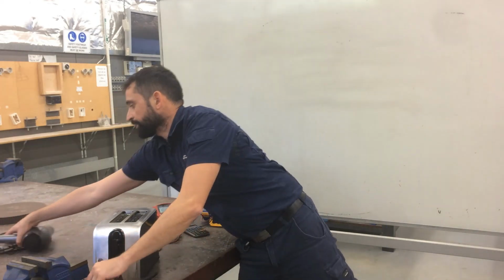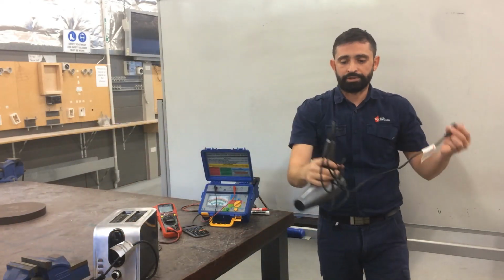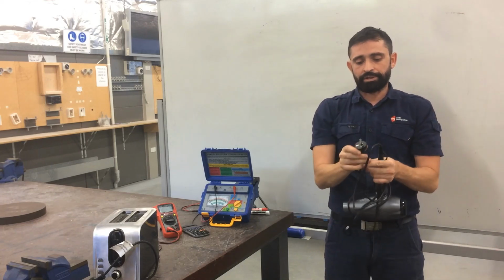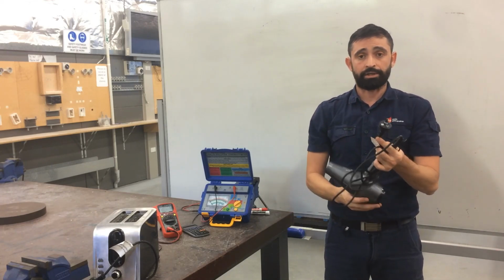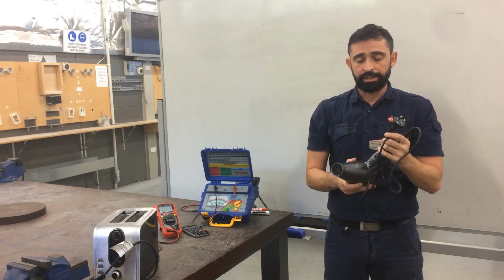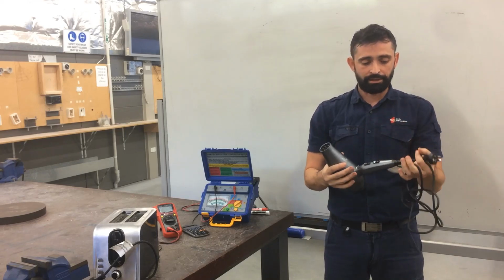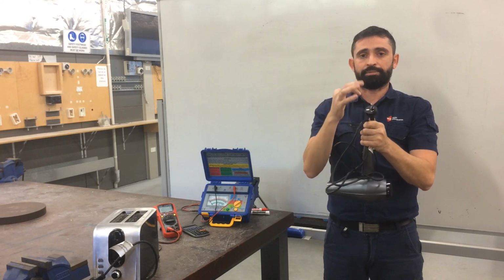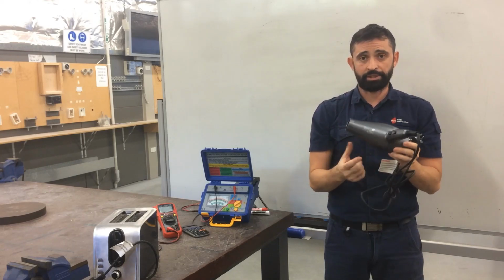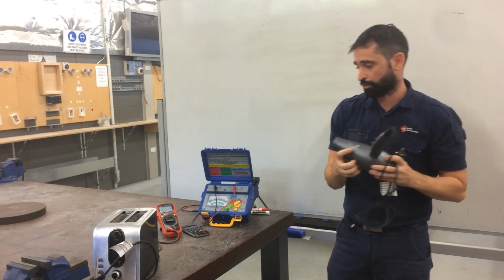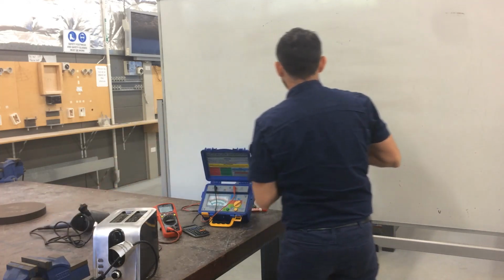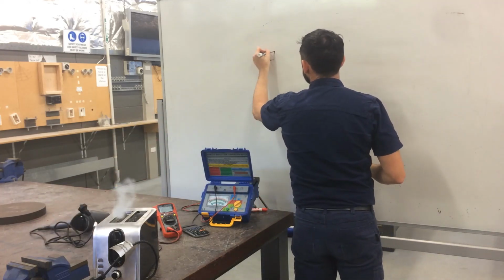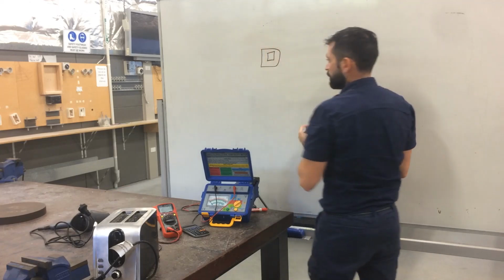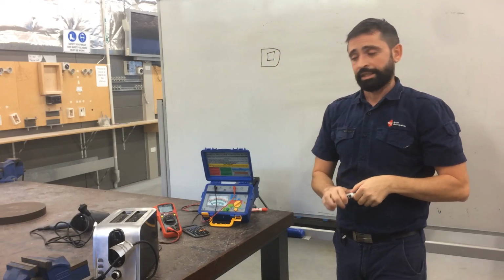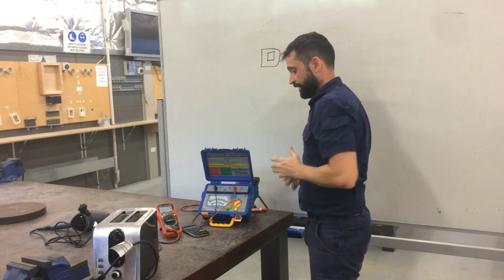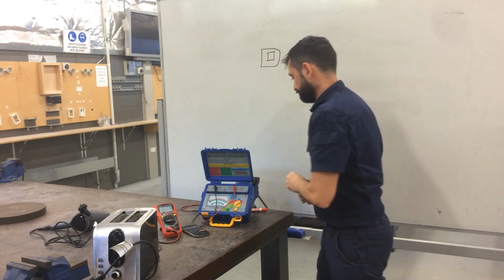Now I've got a class 2 appliance here, and the difference with a class 2 appliance is it doesn't rely on the earthing system, and it doesn't only rely on its basic insulation for protection against electric shock. It also has double insulation, and how we can tell it's double insulation is that it's missing the earth pin. It also has the symbol for double insulation on the base here, which is a box within a box. So if you see that symbol on any appliance, you'll know it's a class 2 appliance, and it doesn't rely on the earthing system. The earthing system's out of the equation.